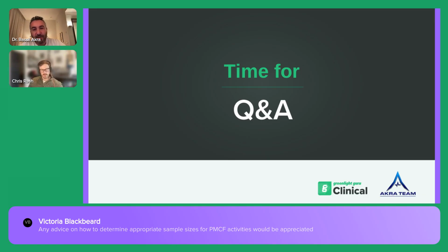So this is a very good question. It's not that easy to define a sample size, like telling you take 100, take 200. I can't answer it as such because it's always relying on what are the questions that we are trying to address in which period of time. So for a sample size, my recommendation is always to consider the patient population, the sales number that you have per year, the available market, and then use your key safety and performance criteria that you are trying to address and involve a statistician to justify your sample size.